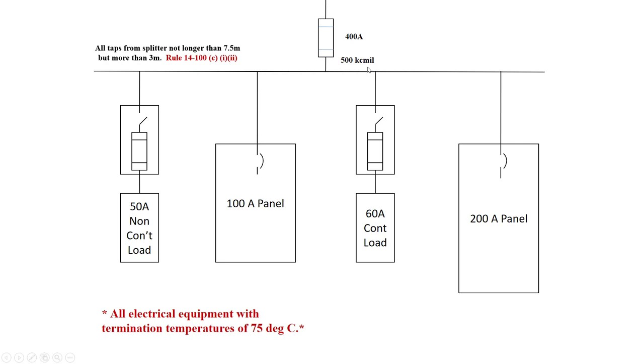The second part of this rule says suitably protected from mechanical damage, not more than 7.5 meters long, terminates in a single overcurrent device rated or set at a value not exceeding the ampacity of the conductor. Beyond the single overcurrent device, the conductor shall be permitted to supply any number of overcurrents. Let's start out here.